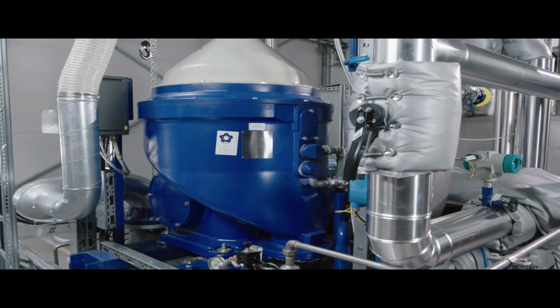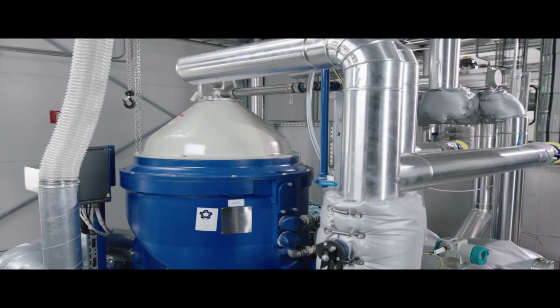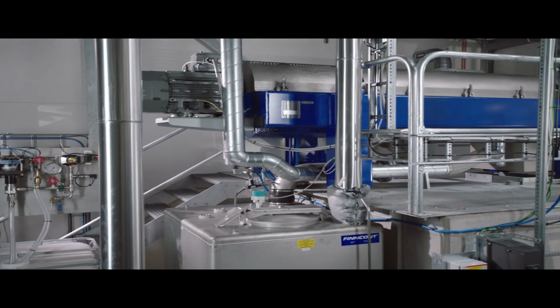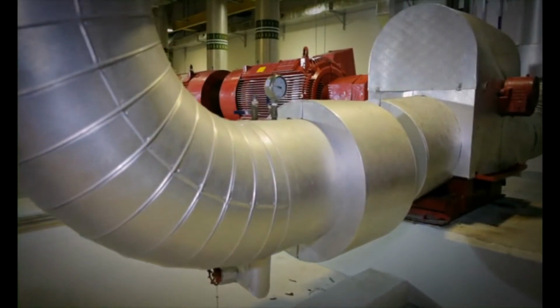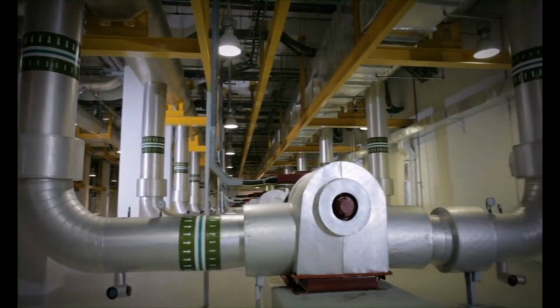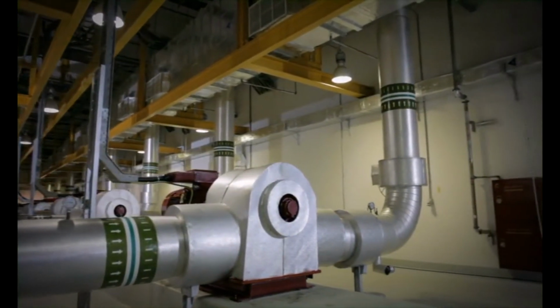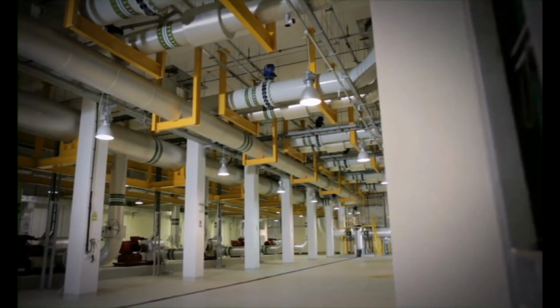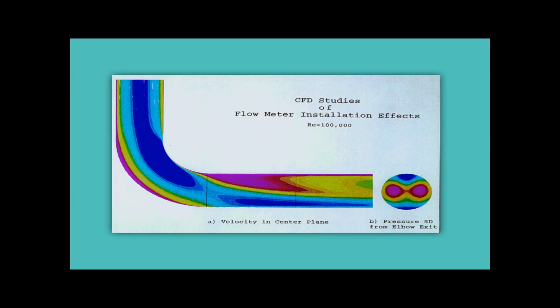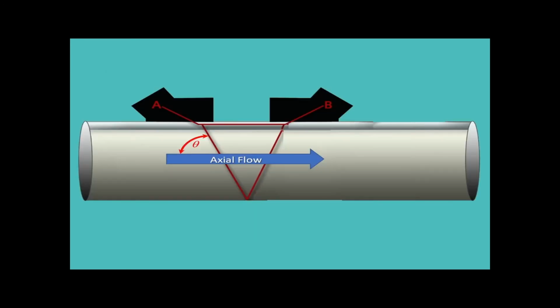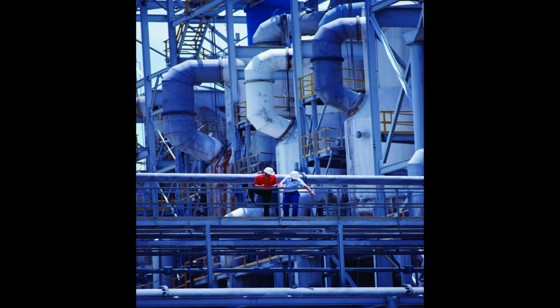To now get down to the nitty-gritty. Let's face it, many flow measurement locations just don't provide sufficient straight piping. So what can you do to mitigate the effects of these locations where the pipe run is limited? First, keep in mind that just because there is limited straight pipe, it doesn't mean your flow meter won't operate. But there are 2 conditions that can degrade flow meter accuracy. The first is the likelihood of a distorted, non-symmetrical flow profile. This will affect proper Reynolds number compensation. And second, the presence of non-axial flow or crossflow can and will produce calibration errors in all area averaging flow meters. So what can you do about it?